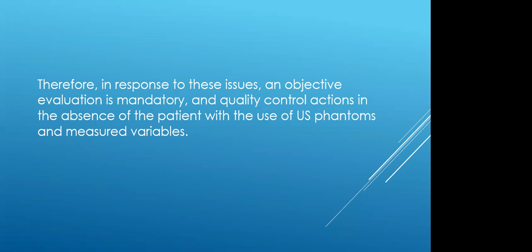But the things that you probably would need to measure are not too many to have good working equipment, right? The next slide will try to give you an idea of what things you probably need to measure. What this table basically gives you is the item to be measured and the detail: what you are actually coming up with, and how important it is, or what causes it. So in most cases, you want to know the axial resolution, the lateral resolution, and also the beam thickness, or you want to look at registration or the dead zone, and you also want to look at sensitivity, right?